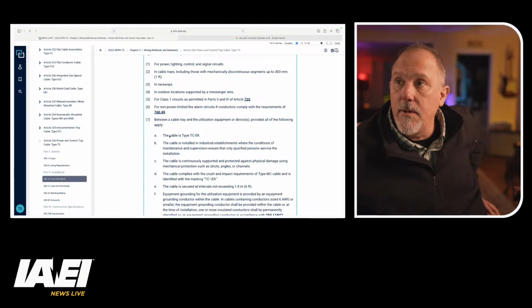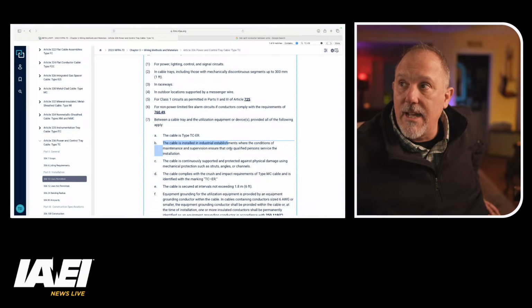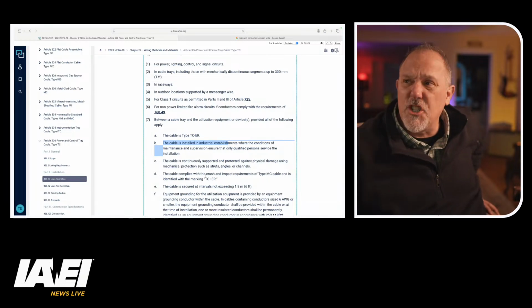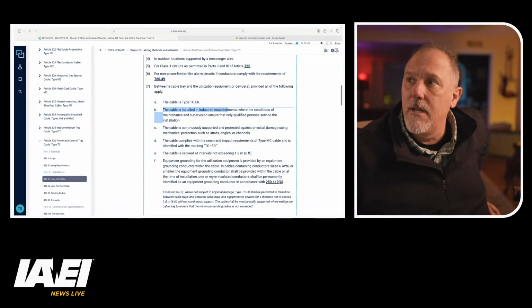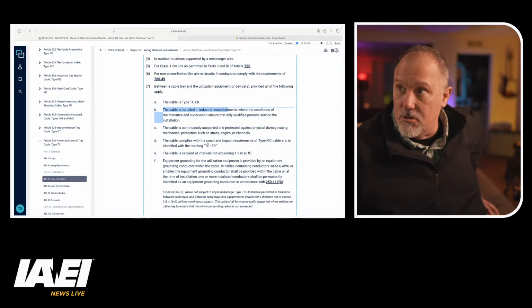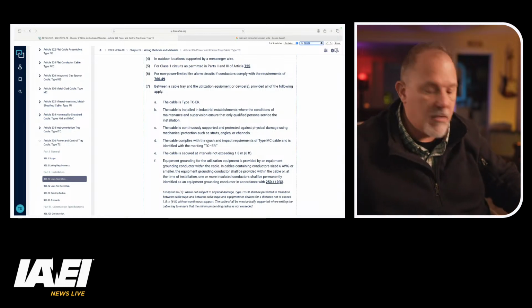There it is. The cable is type TCER between a cable tray and utilization equipment or devices, provided all the following apply: the cable is type TCER, installed in industrial establishments, continuously supported, and complies with the crush and impact requirements, etc. It has to be marked with all that.